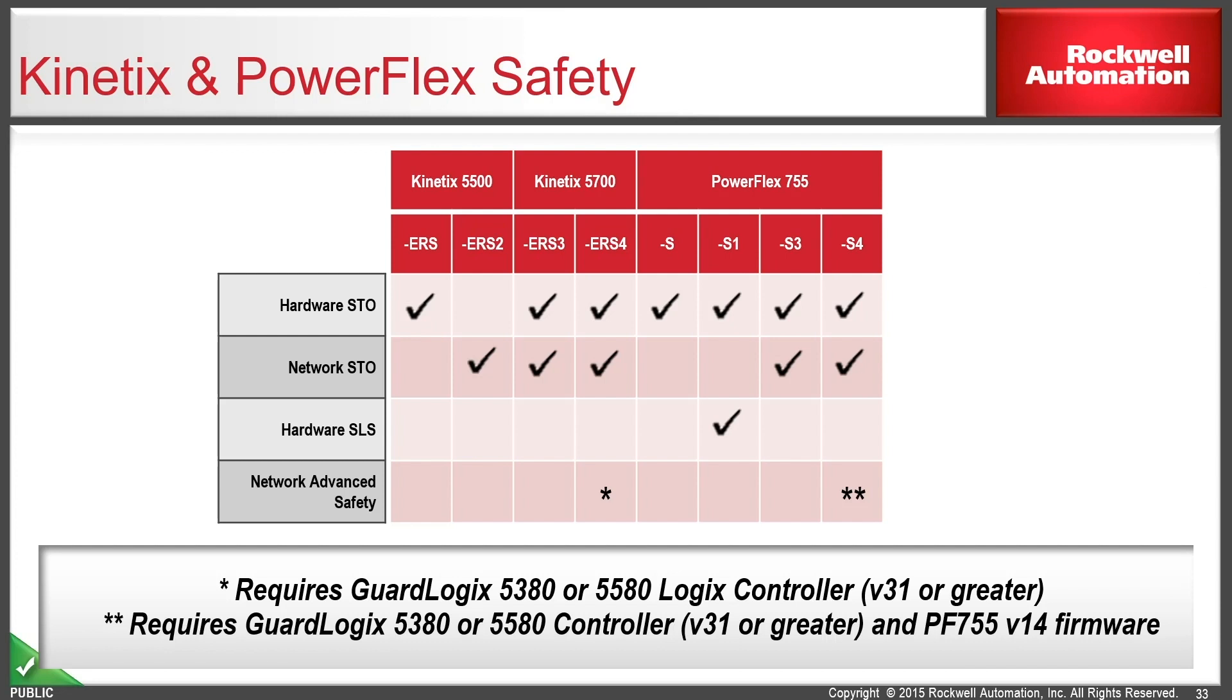There are a couple of caveats with that though. You do need to use an L8 safety controller whether that's the compact GuardLogix or the full-blown GuardLogix controller with version 31 or higher of Studio 5000. And then you also would need, in the PowerFlex's case, you would need to use firmware version 14 for the drives.